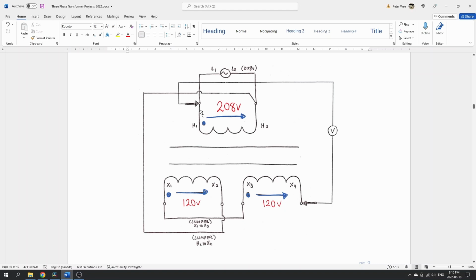So as we went through that circuit from this point, 208 minus the 120, right? Opposite direction through this winding. So minus the 120 plus the 120. Well, then the voltage between these 2 points is going to be limited to this 208 volts. Because we have this connection here and we've got the polarities of the secondaries opposing each other, these two 120s are canceling each other out, leaving us with the 208 volts. Again, probably the last thing that we want to start with as a student. It would have been better to actually see the additive voltage or see the subtractive voltage. So we've got to do one thing to change this. So let's go back to the lab and we'll see which one thing we need to change on our transformer.